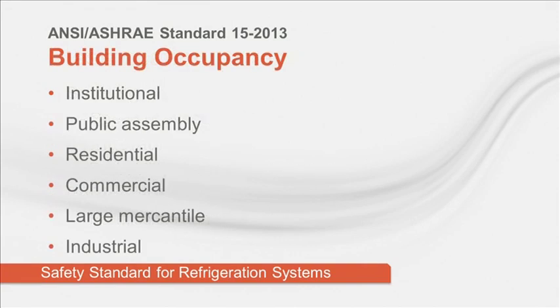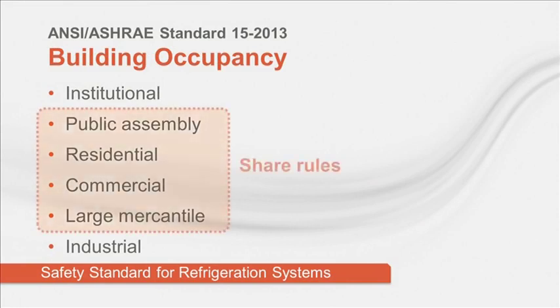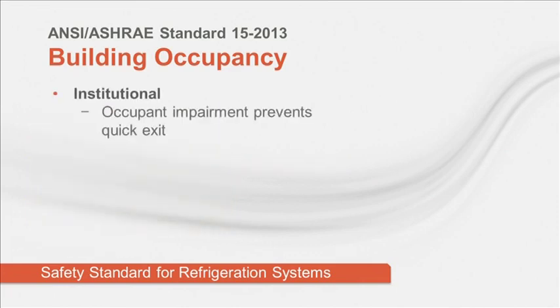For the purposes of Standard 15, ASHRAE divides occupancies into 6 categories. In practice, the 6 categories can be reduced to 3 types because the same rules apply to public assembly, residential, commercial, and large mercantile. Special rules apply to the last 2 occupancy types, institutional and industrial. Institutional occupancy includes facilities where the occupants have difficulty evacuating, such as hospitals and jails. Refrigerant safety rules are more restrictive for this application.